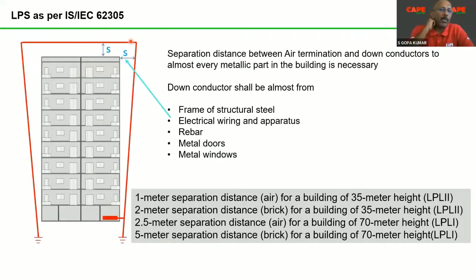Now, this is what is explained in IEC 62305. Once we explain this subject to the construction site or to the clients, most of the clients say that, no, this is not required, you leave it. We don't want to calculate the separation distance, or we don't want to consider separation distance. Please note that if you don't consider separation distance, your lightning protection system is inefficient. Lightning may hit the air termination, but instead of the current flowing through the down conductor, there will be flashover between the air termination and the metallic parts of the building. As a result, current is going to flow through your building, which may destroy so many things.